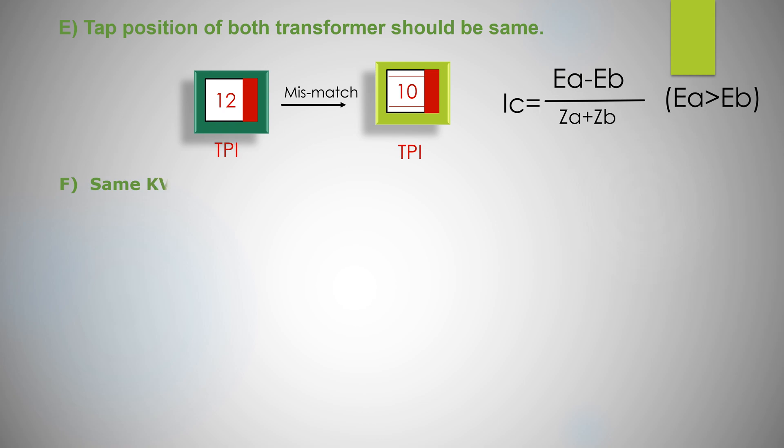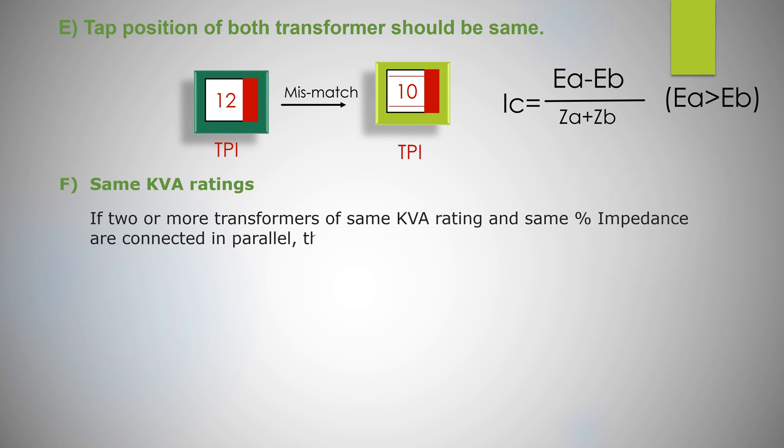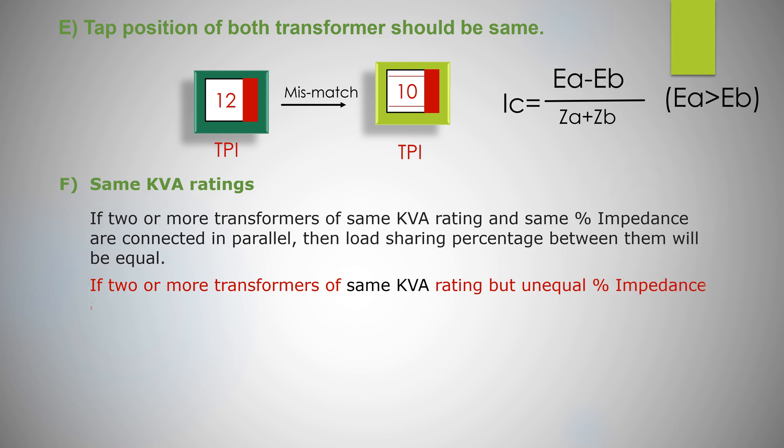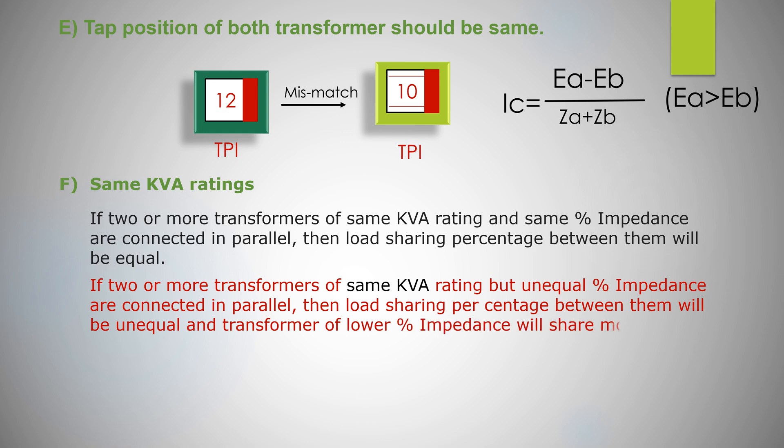KVA rating should be same. If two or more transformers of same KVA rating and same percentage impedances are connected in parallel, then load sharing percentage between them will be equal. If two or more transformers of same KVA rating but unequal percentage impedance are connected in parallel, then load sharing percentage between them will be unequal and transformer of lower percentage impedance will share more load.